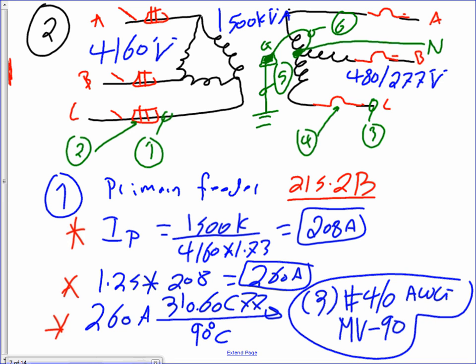Now, Dirk, I don't know if you've ever heard of MV-90. MV-90, guys, is a medium voltage cable temperature rated for 90 degrees. Why did we use a medium voltage cable? Because look at the voltage, 4,160 volt. Can I use THHN? No. Why? Because THHN is not rated for more than 600 volt. Did you guys hear me? THHN wouldn't cut it here.